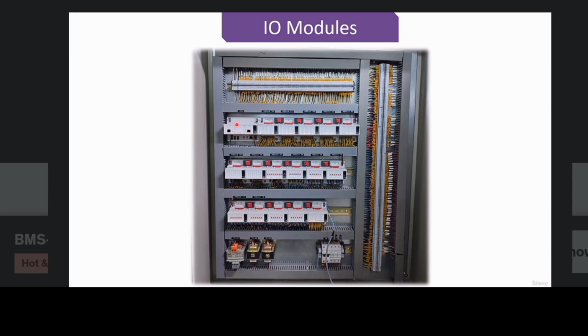Every manufacturer uses different communication protocols. The one which is used here is LON. Usually Honeywell now uses the panel bus communication protocol for communication between the DDC controller and the expansion I/O modules. Some other vendors use open protocols like BACnet MSTP and Modbus.